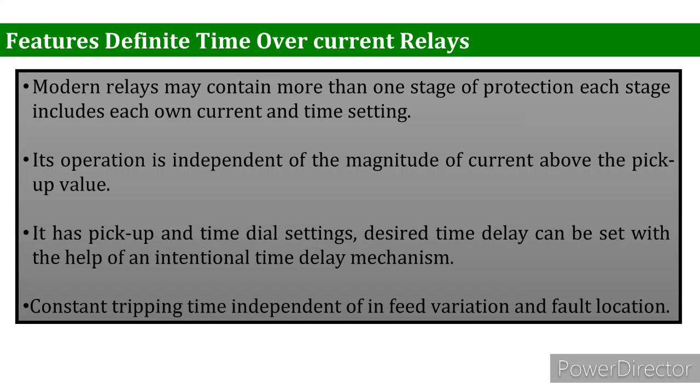If we talk about some major features of the definite time overcurrent relay: first, its operating time is constant. Secondly, its operation is independent of the magnitude of the current above the pickup value, that is I pickup.